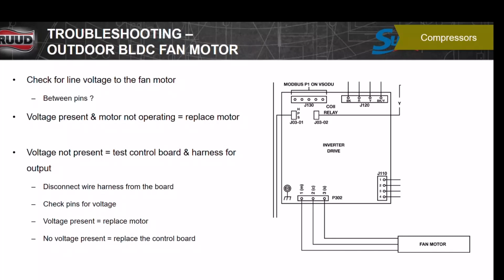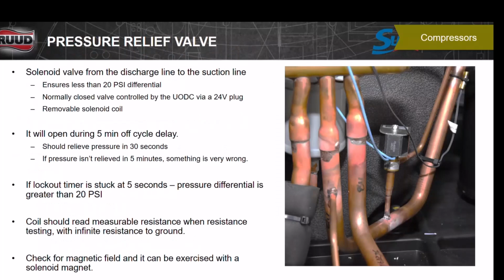Didn't get the question, so I'm going to throw it out there too. Can this unit run on just the contactor? Can we bypass the inverter and run this unit if the inverter's bad? We just run it at high speed. The answer is no, because the motor runs through the inverter, so we wouldn't be able to run the motor. And it runs off a PWM signal, so we can't jump it out. The answer to that's no, so we don't go reinvent the wheel. Someone will find a way to rip all this stuff out and make this unit run normal, like a regular system, but I don't want to be involved in that.